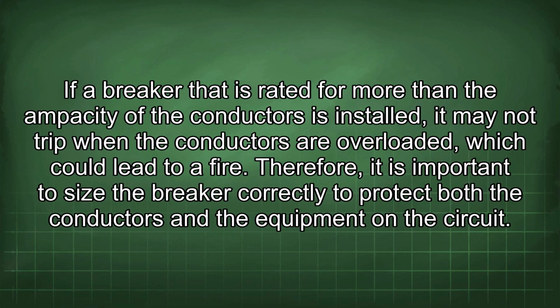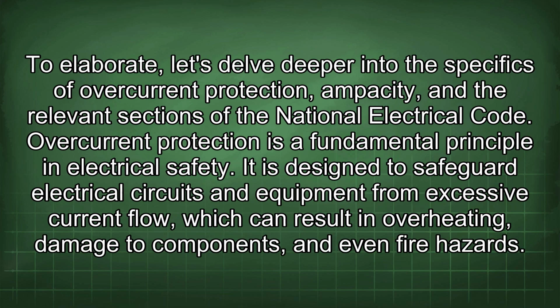If a breaker that is rated for more than the ampacity of the conductors is installed, it may not trip when the conductors are overloaded, which could lead to a fire. Therefore, it is important to size the breaker correctly to protect both the conductors and the equipment on the circuit. To elaborate, let's delve deeper into the specifics of overcurrent protection, ampacity, and the relevant sections of the National Electrical Code. Overcurrent protection is a fundamental principle in electrical safety.